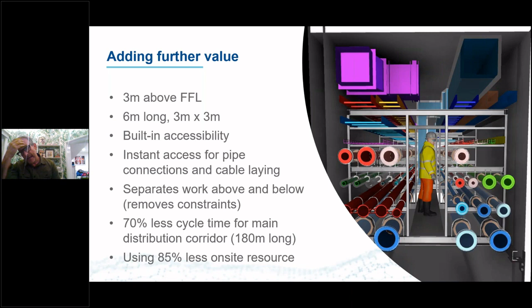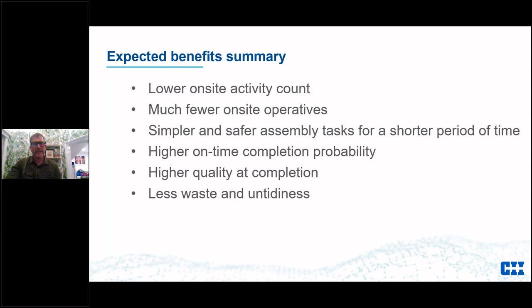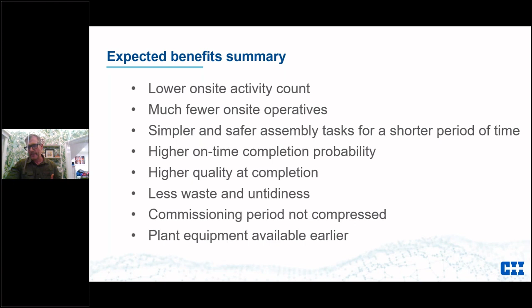So the expected benefit summary: lower on-site activity count, much fewer on-site operatives, simpler and safer assembly tasks for a shorter period of time, higher on-time completion probability, high quality completion, less waste and untidiness, commissioning periods not compressed, and your prime movers, your plant, is available earlier. So you can use that plant for either commissioning or heating the building, etc.